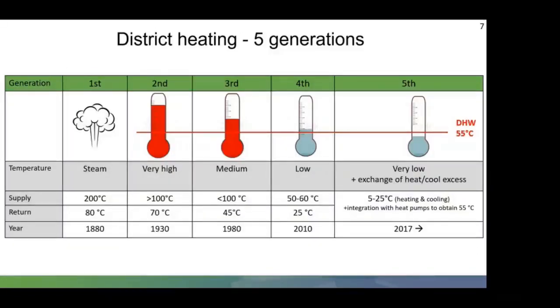So, district heating, five generations. The first, second, third, fourth and fifth generations. As you can see, the temperatures have decreased over the last 130 years to what we recognise now as 4th generation. 5th generation is what we should be trying to achieve, with the integration of renewable technology, increased control and live data collection, as sustainable as possible. The more information you can gather from a district heat network, the more efficient you can make the system, by looking at variations in the outside temperature, the inside temperatures, what the buildings are working at, and the flow and return temperatures.